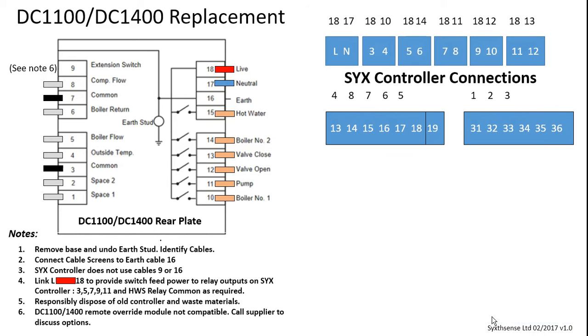With regards to the power arrangements, we remove the live power supply terminal 18 on the DC controller and connect that into the live connection of the SYX product. We also then make switch feed connection links into terminals 3, 5, 7, 9 and 11 from that live power supply. The SYX controller does not provide its own switch feeds.